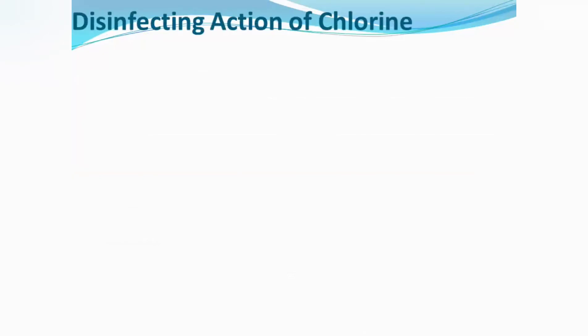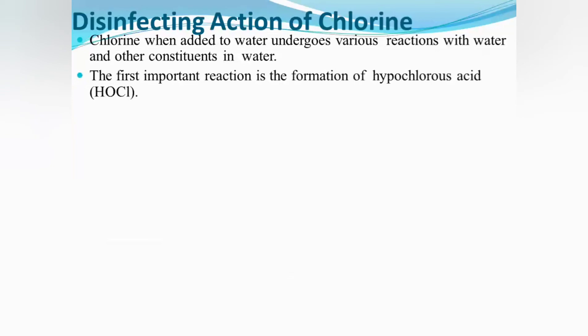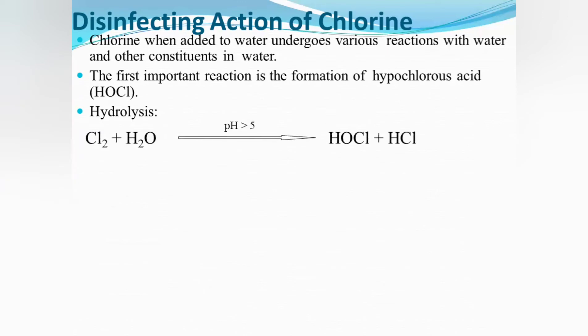Disinfecting action of chlorine: chlorine when added to water undergoes various reactions with water and other constituents. The first important reaction is the formation of hypochlorous acid, HOCl, through hydrolysis: Cl2 + H2O → HOCl + HCl.